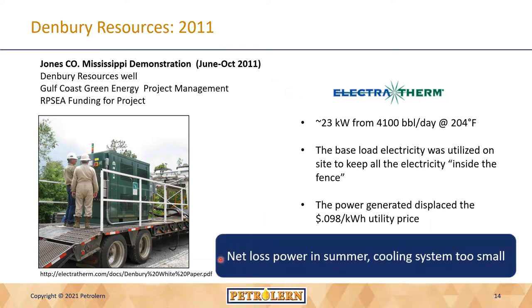It's important to point out that they had a net loss of power in the summer. This is because it's an air-cooled system, which means in summer you're trying to reject heat to a hot, muggy 90 to 100 degrees Fahrenheit environment. When your resource is only 204 degrees Fahrenheit, that doesn't work well. The cooling system was actually made too small, resulting in a net loss of power in summer. That's why the project started in June and ran through October, but it ultimately wouldn't work out because it could only run about 4 to 5 months out of the year.